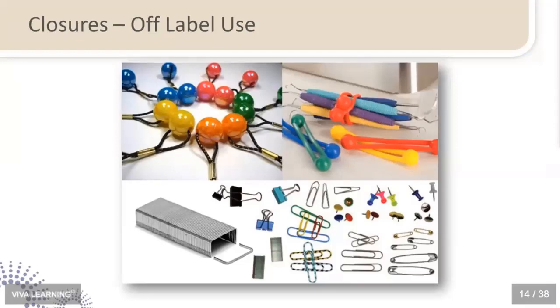Okay, so we cannot use any type of elastic band, whether it's made for instruments or by a dental company like you see on the right. We can't put our instruments together in a bundle and put them in the steam sterilizer, or in the ultrasonic for that matter, because the steam or the ultrasonic cavitation isn't going to be able to get to the middle. So you can't band your instruments together. That is not an approved use. That's one of those off-label uses by the FDA.